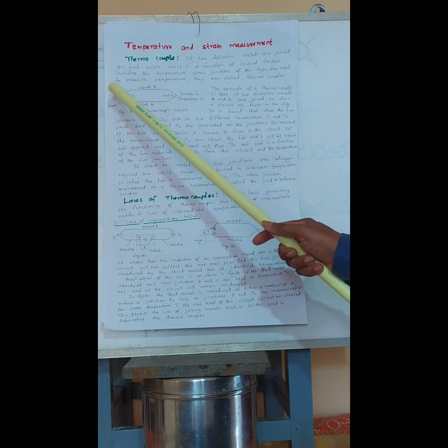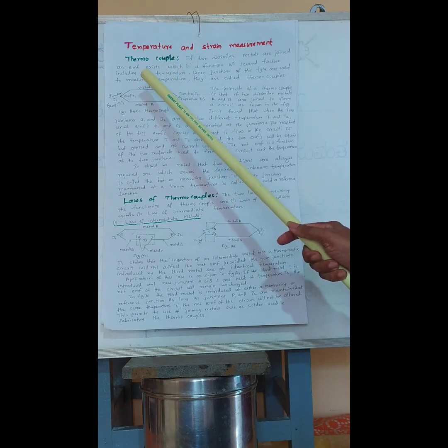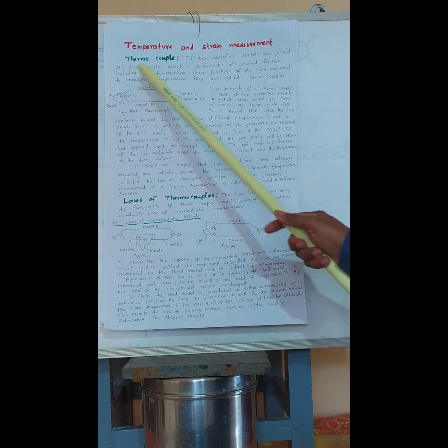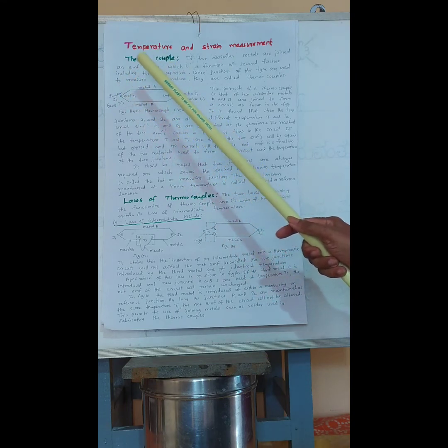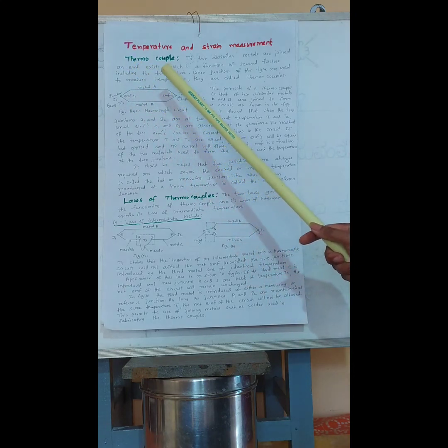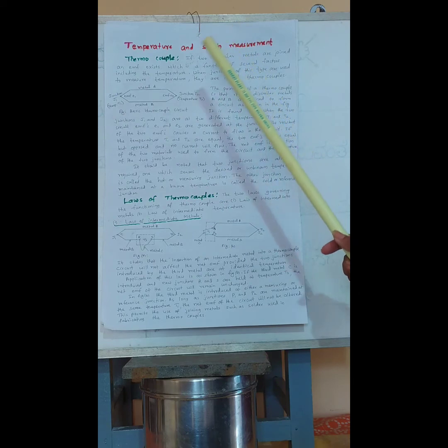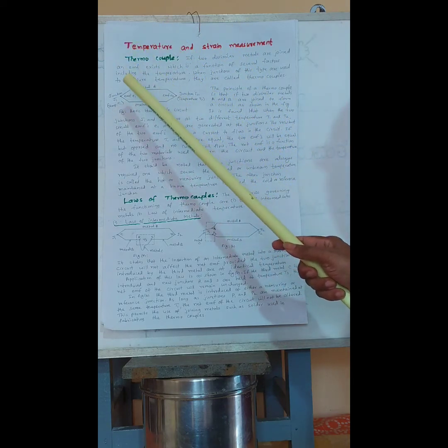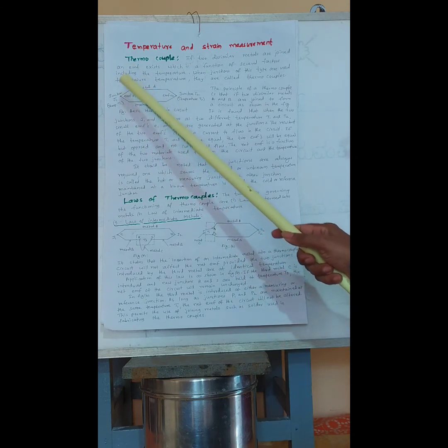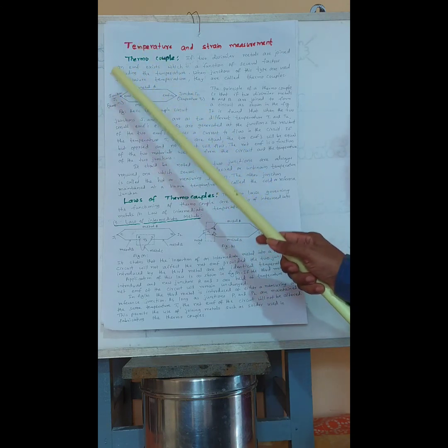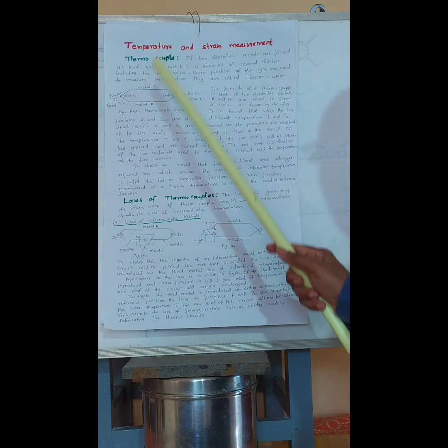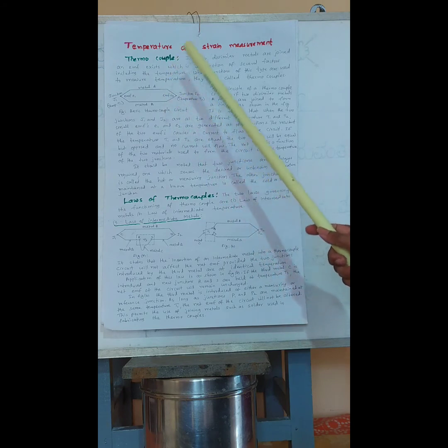If the temperatures T1 and T2 are equal, the two EMFs will be equal but opposed and no current will flow. The net EMF is a function of the two materials used to form the circuit and the temperature of the two junctions. It should be noted that two junctions are always required. One which senses the desired or unknown temperature is called the hot or measuring junction. The other, maintained at a known temperature, is called the cold or reference junction.